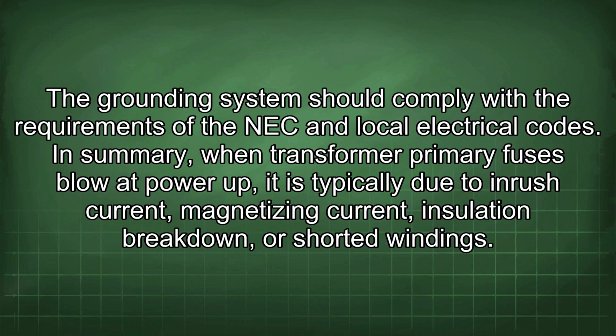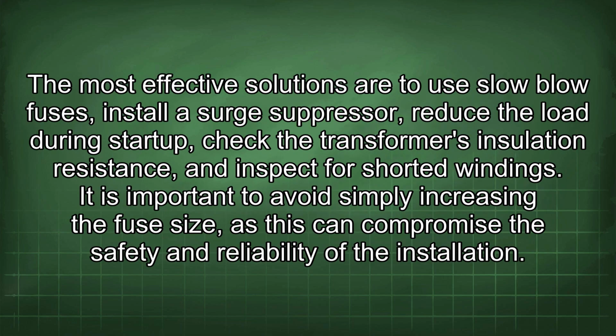The grounding system should comply with the requirements of the NEC and local electrical codes. In summary, when transformer primary fuses blow at power up, it is typically due to inrush current, magnetizing current, insulation breakdown, or shorted windings. The most effective solutions are to use slow-blow fuses, install a surge suppressor, reduce the load during startup, check the transformer's insulation resistance, and inspect for shorted windings.